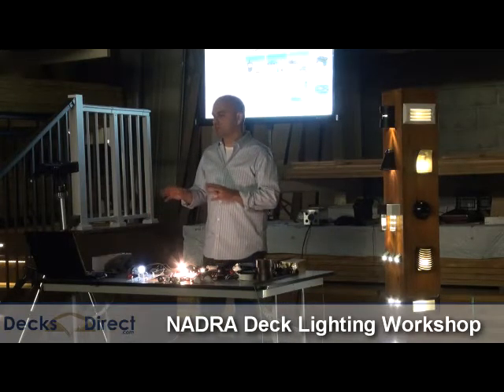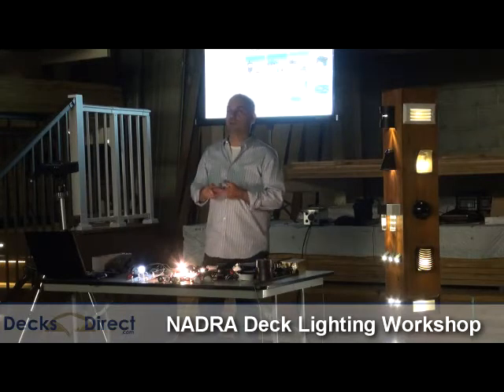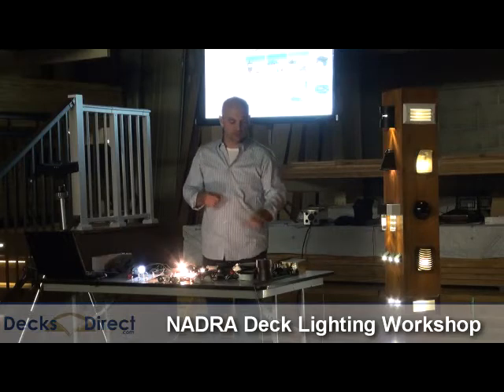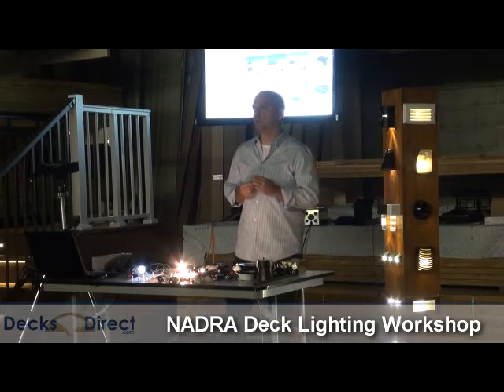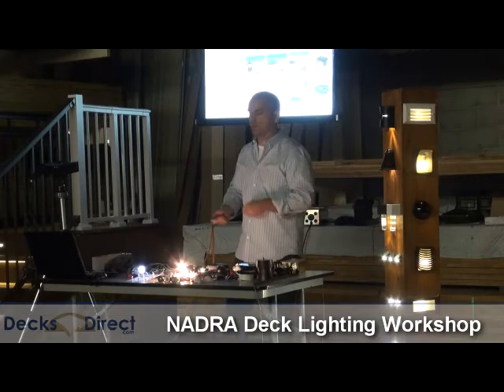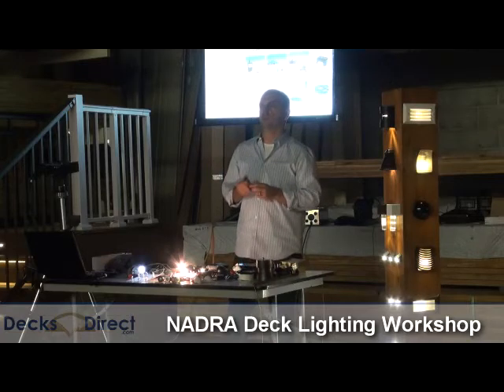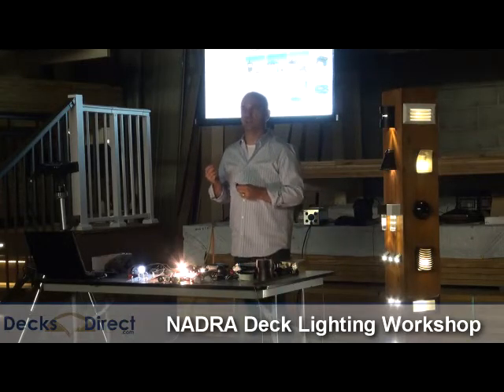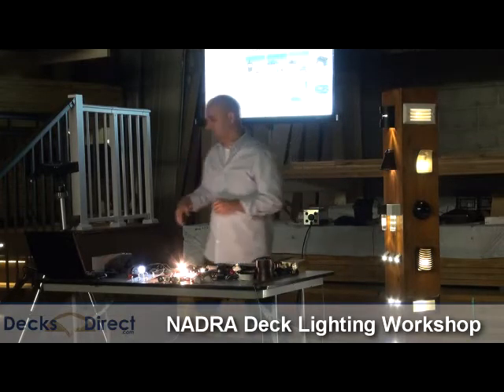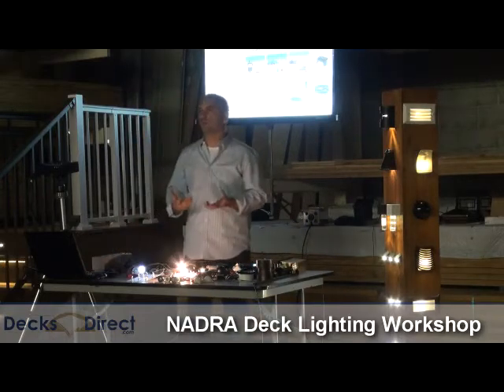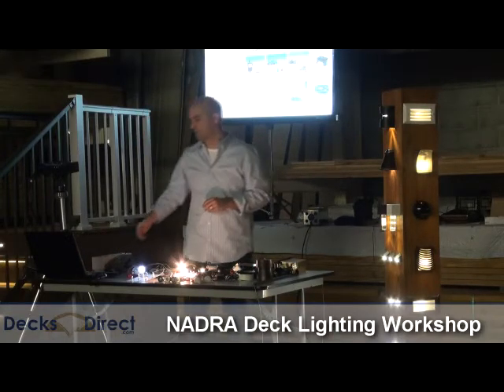Probably the last thing on controlling this stuff: anytime you install one of these systems, test it before you start putting on silicone wire nuts. If you have reverse polarity or any other issue, these silicone wire nuts will drive you nuts with all the grease getting over everything. So test it before you nut everything off—that's from personal experience.